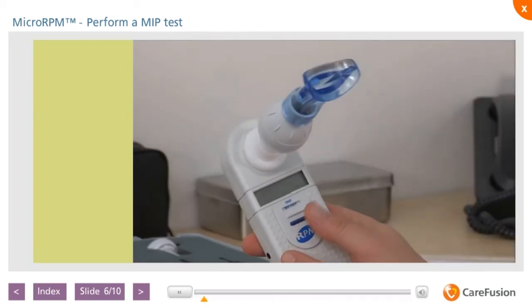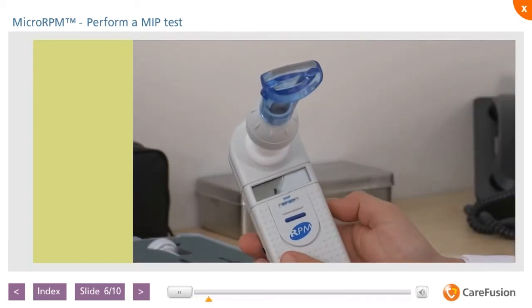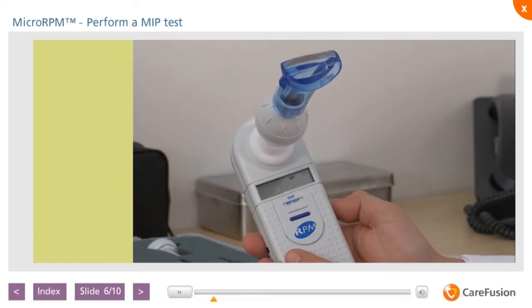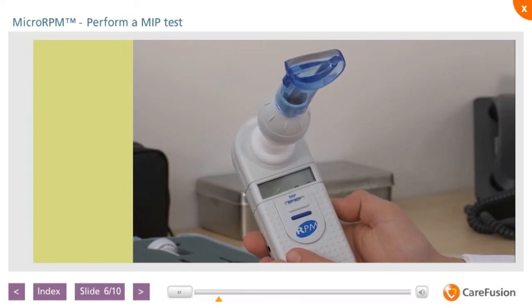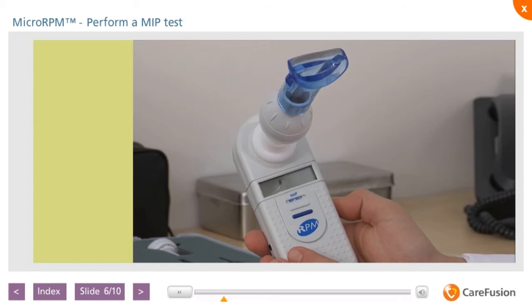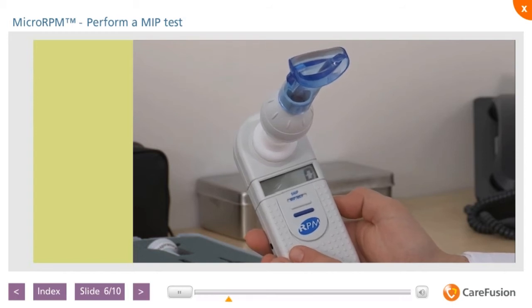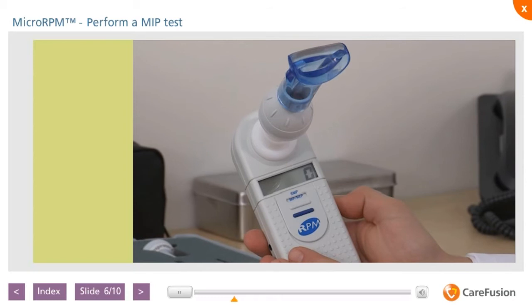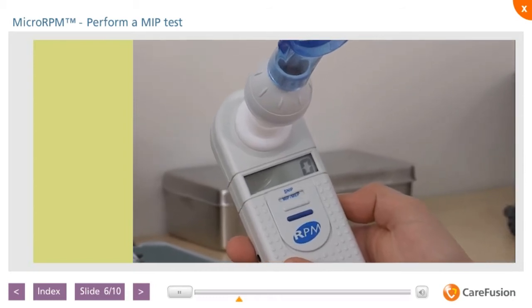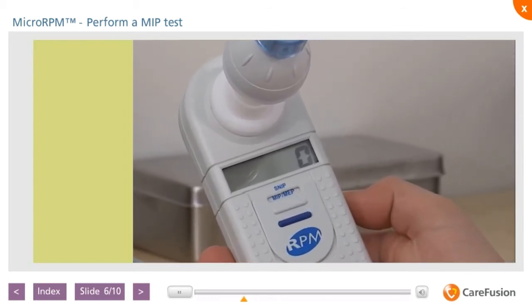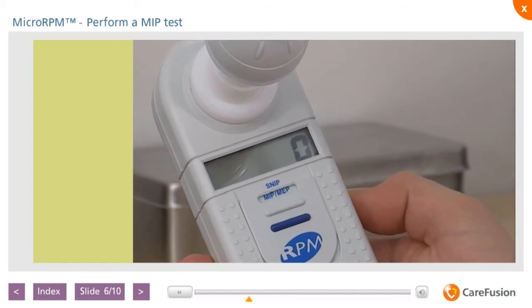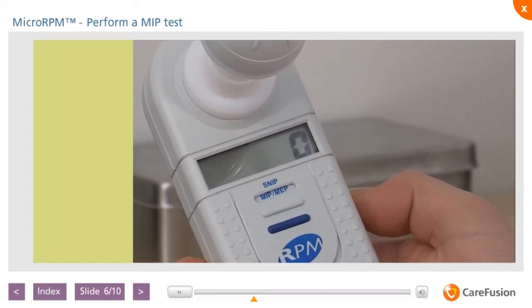Once the correct assembly is in place, slide the switch on the front of the unit to the MIP-MEP position. The unit will automatically zero after approximately 4 seconds, and the screen will display the digit 0. While the unit is zeroing, it's important not to apply any pressure to any part of the mouthpiece or filter assembly. The unit is now ready to measure PI max or PE max measurements.